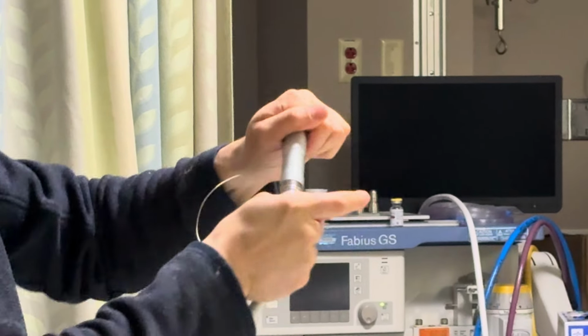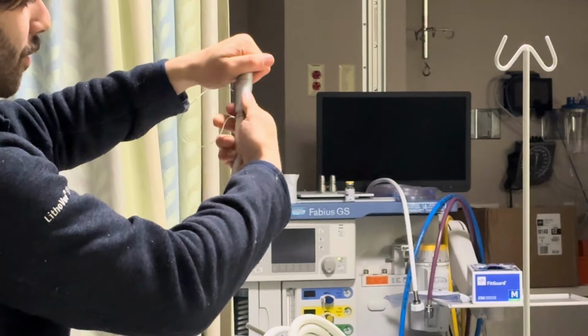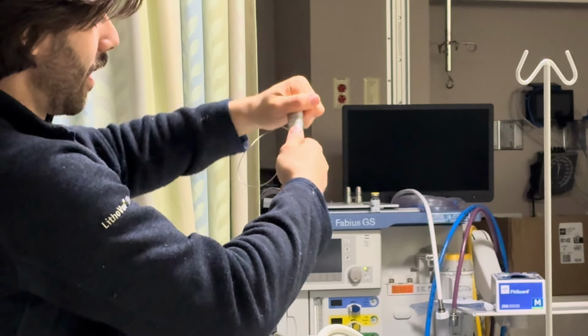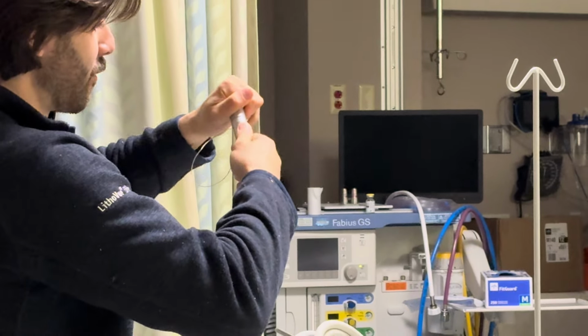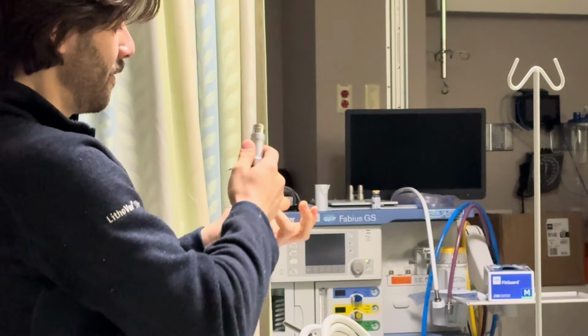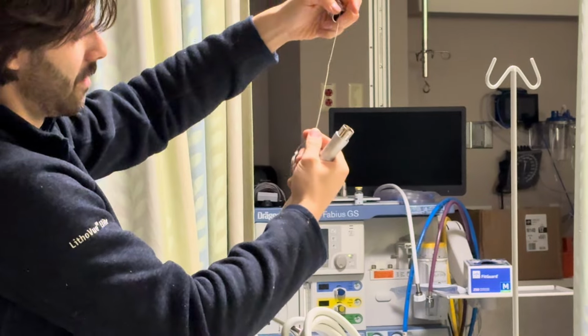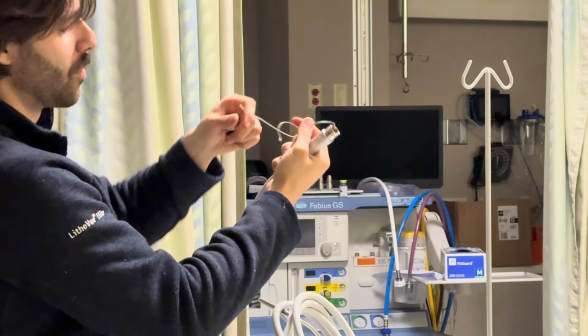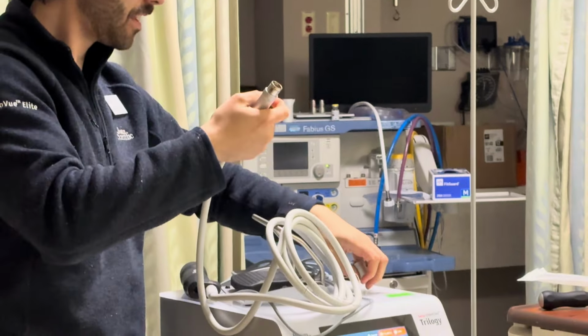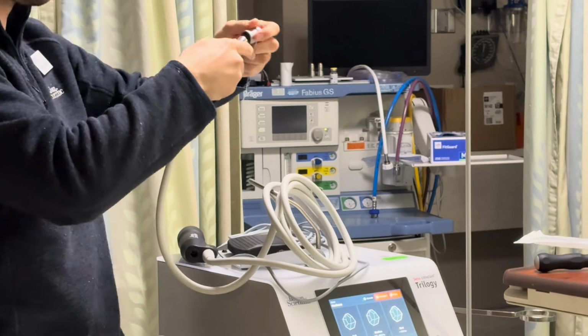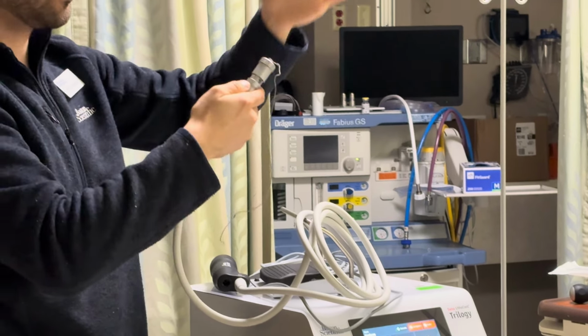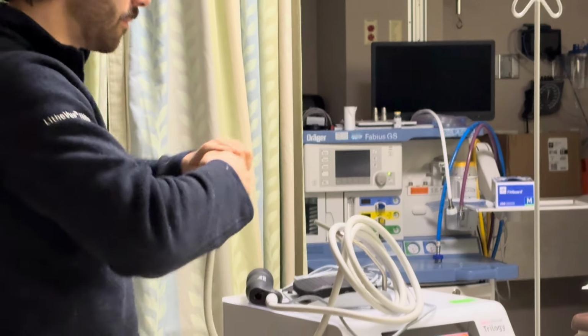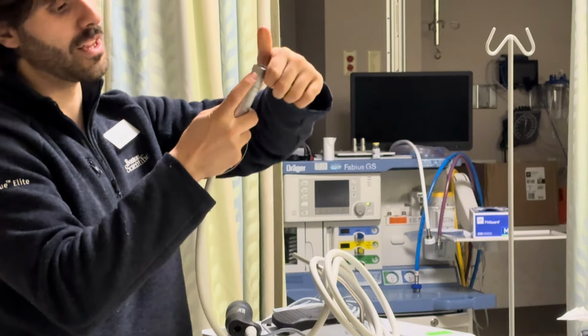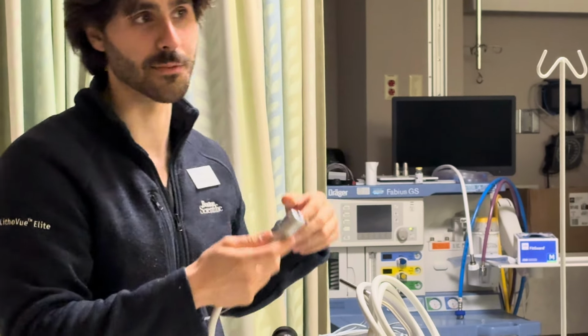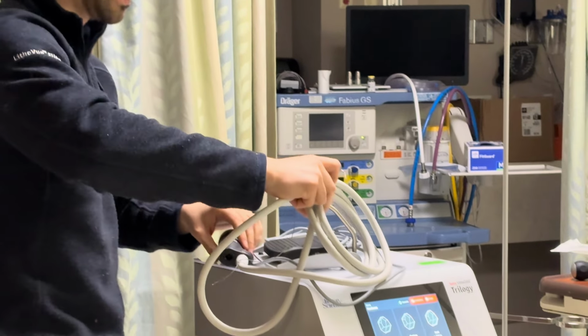A lot of people just try to force it out and it's not going to come out. You got to pull the sheath down and then up. Just watch out for your fingers. Some people get caught up in this, and we'll take care of this later too. And once you're done with the case, just make sure you put this back on, because you don't want to sterilize this with this open, because that exposes the electronics of the handpiece.